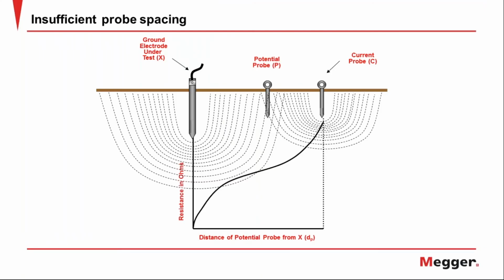This shows you why. Because the current probe has its own electrical field, and if that overlaps with the electrical field you're trying to measure, it fogs the clarity of your graphics, and you can't reach a conclusion as to the actual resistance measurement of your test ground. That's the reason for it.